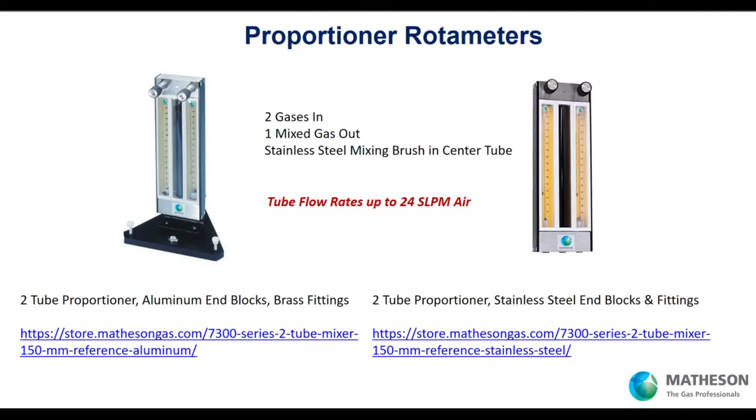There's a whole other world of digital mass flow — a mass flow device can range from $2,000 to $3,000, and the controller is $3,000 to $4,000. Two mass flow devices and a controller puts you near $8,000 for that solution. With our rotameter-based proportioner, two gases flow in, meet at the top, and tumble down a mixing brush to the point of use. This aluminum end block unit with brass fittings is less than $1,000. Here's the same thing with stainless end blocks — a little more, but very cost effective.